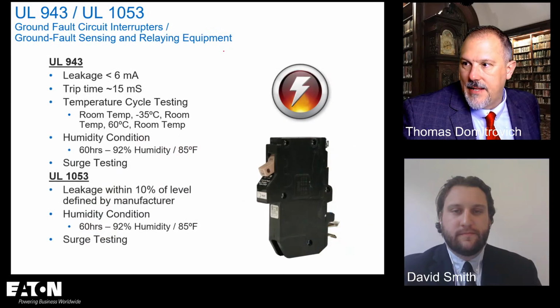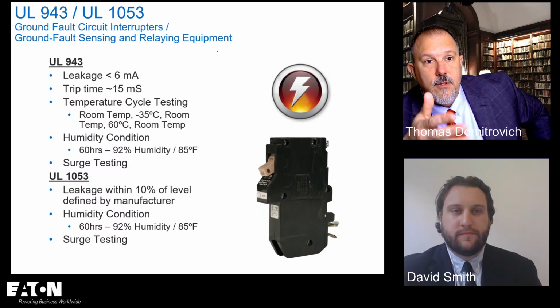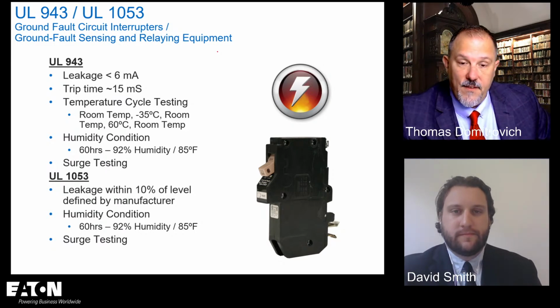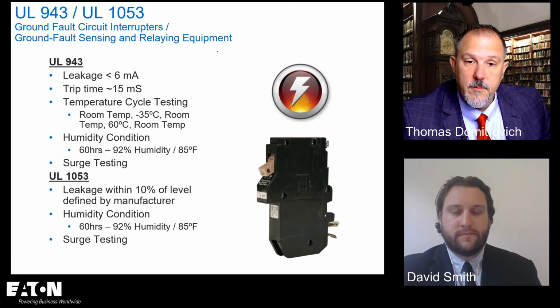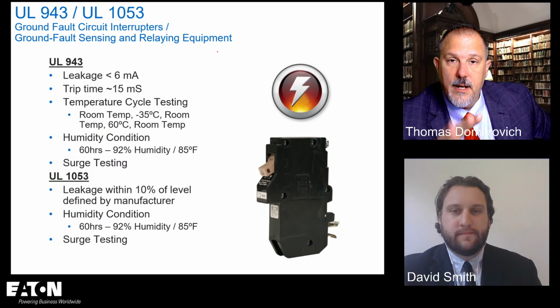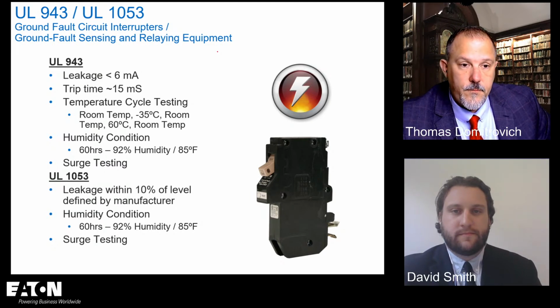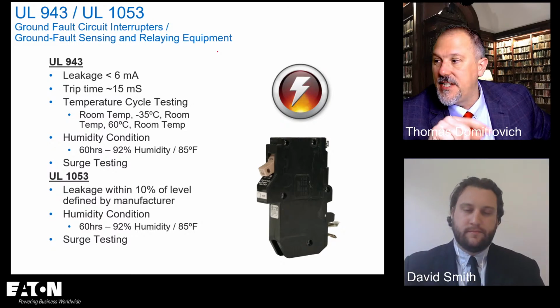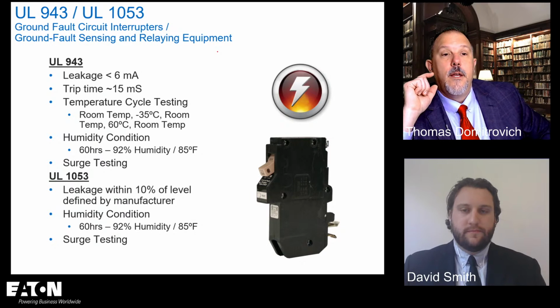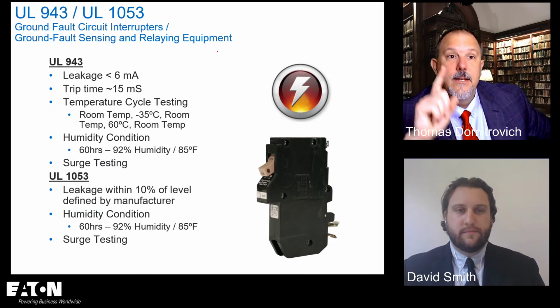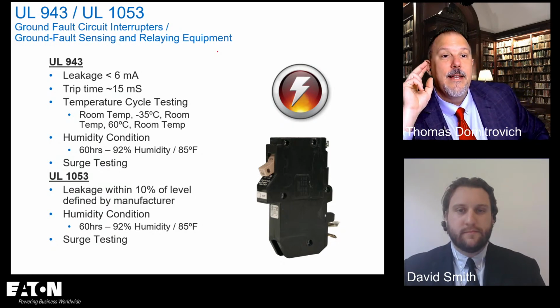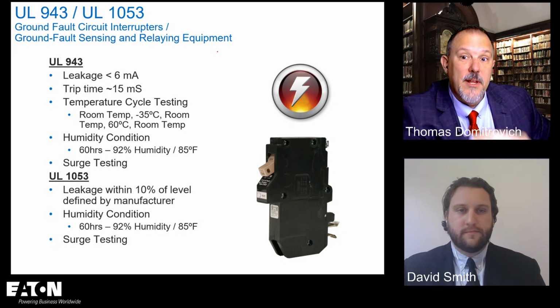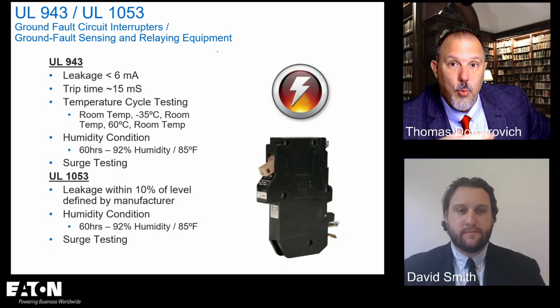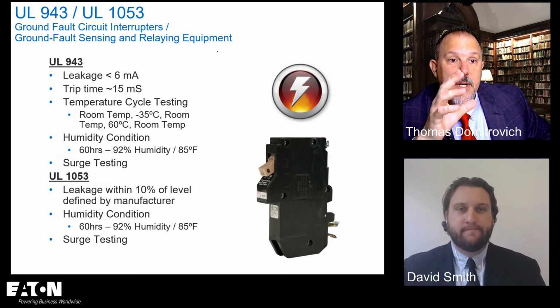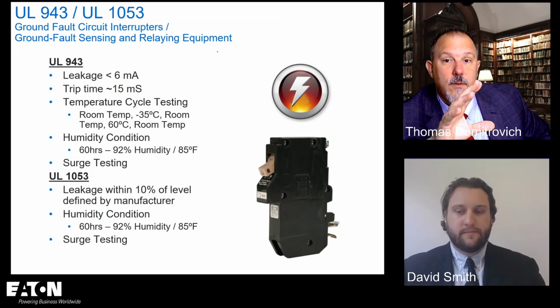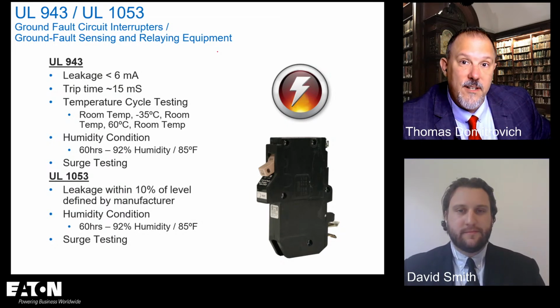Okay, so that's that. And then we already said GFCIs are listed to 943. A GFPE is 1053, which is not personnel protection, that is equipment protection. And the level of current that it picks up is determined by the manufacturer or the design engineer. But if I have an AFCI, GFCI circuit breaker, it's listed to 1699, it's listed to 489, it's listed to 943, and there's a couple other standards that it's listed to as well. Very well tested overcurrent protected device. But I can put everything in one device these days.